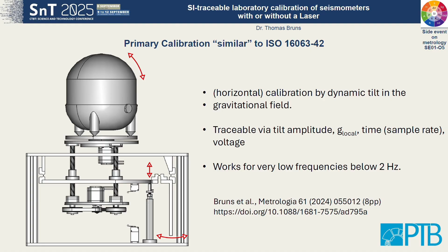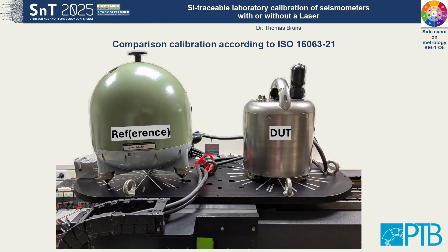You see the publication at the bottom. But it only works up to 2 Hertz, because after that, the whole system is not rigid enough for the higher frequencies and higher accelerations. But nevertheless, it's very reliable, more reliable than the laser interferometric method I showed you before for very low frequencies. But then we have what we call comparison calibration or secondary calibration, where we compare two seismometers. We don't have too many in the lab so far, so I can only show those and not a full bouquet.